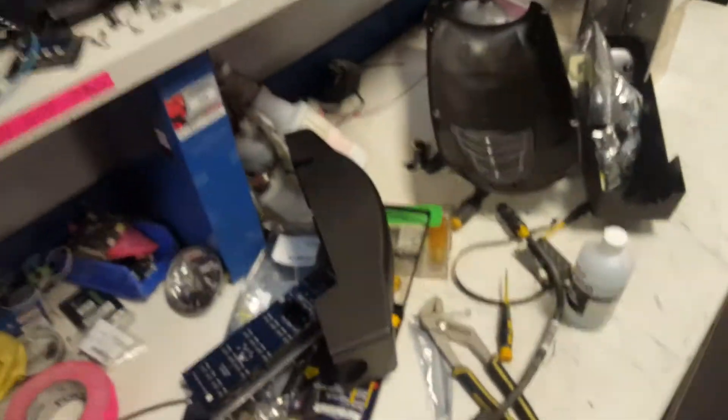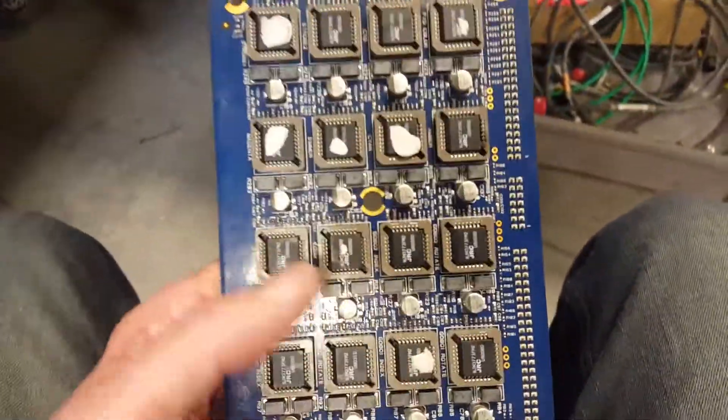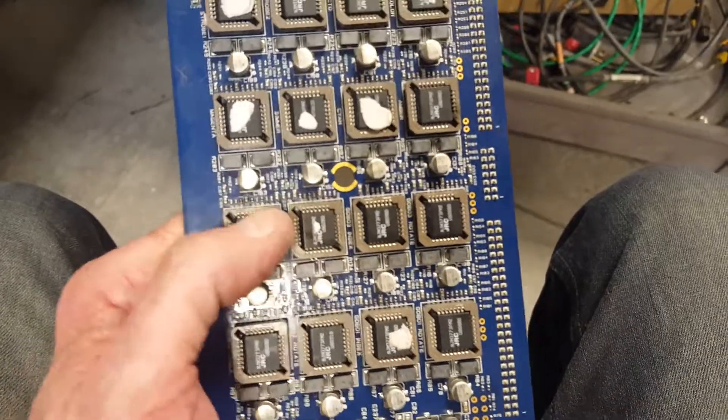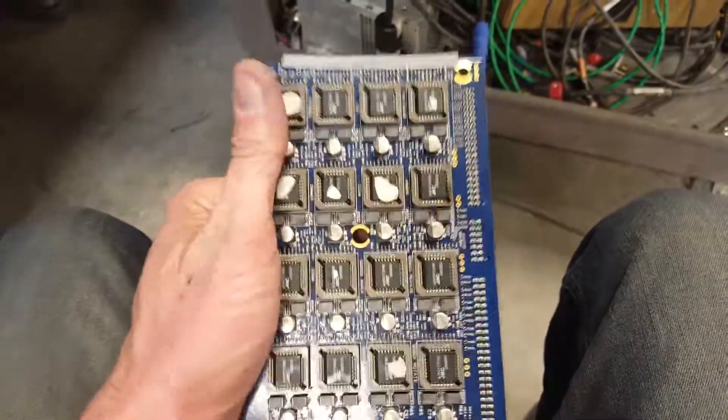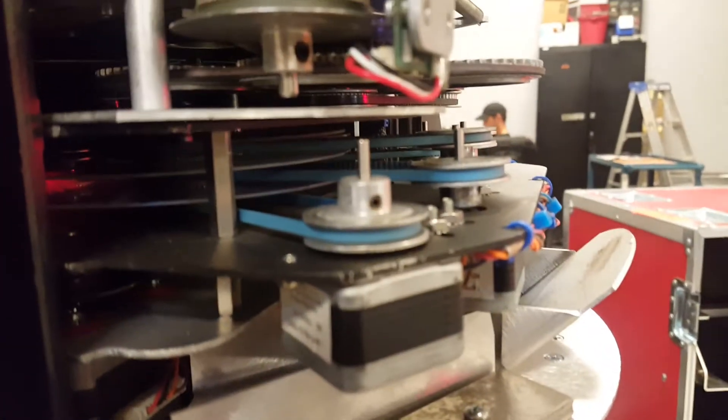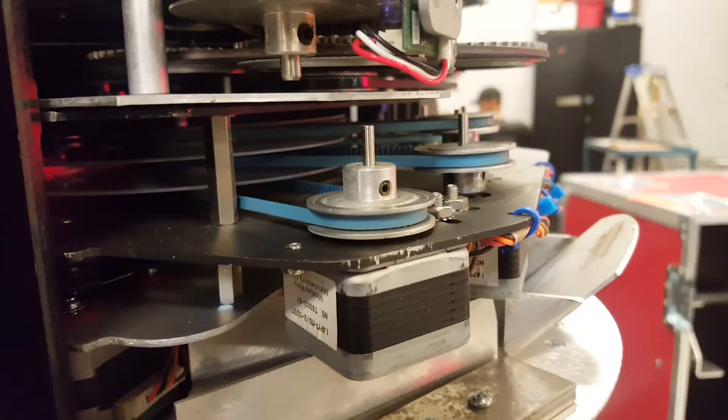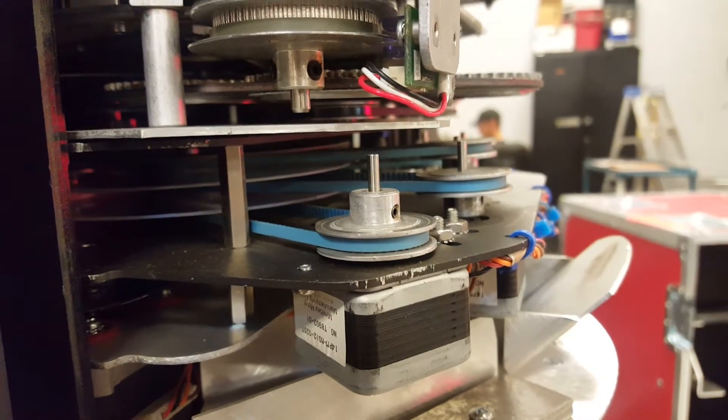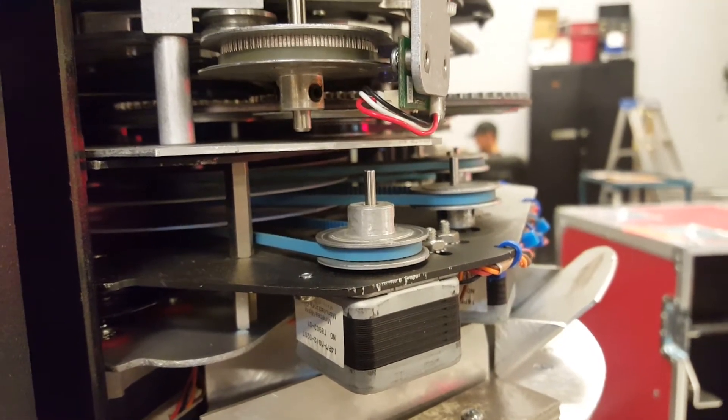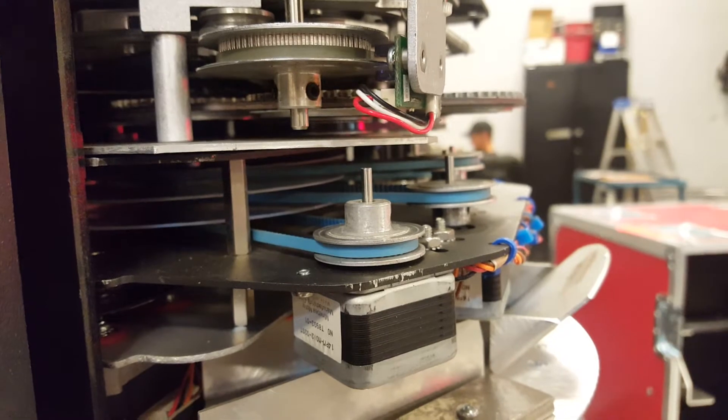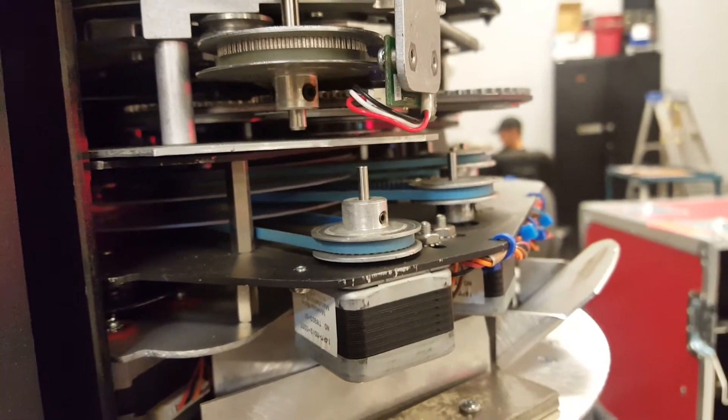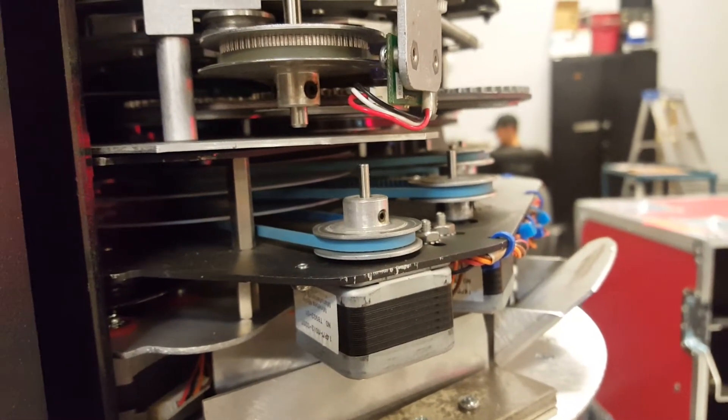As you can see, there are no sockets on the 2500, but on the VL3000 and 3500 spots, the old models all have sockets like these for the motor drivers. Usually when a motor acts kind of like this, moving backwards and forwards, doesn't really know where to go, you see it jerks back and forth.